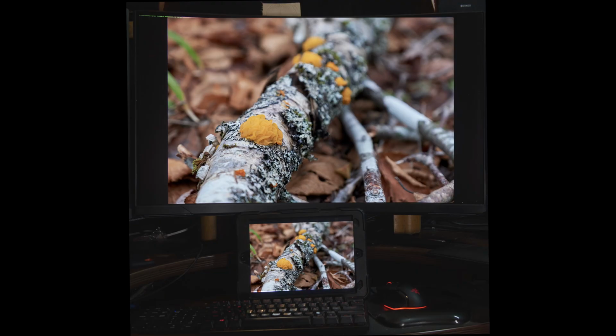I say roughly because no matter what you do, one monitor will produce its image slightly different from the next, just due to differences in how they're made. Even two monitors of the same make and model will produce slightly different images. So our goal is to balance them around a standard of reference, and iDevices, iPads and iPhones, which tend to be excellently factory calibrated, provide such a standard of reference. This means all of your images will look more or less the same on all of your monitors, all of your devices, and the monitors and devices anybody else is using to look at them too.